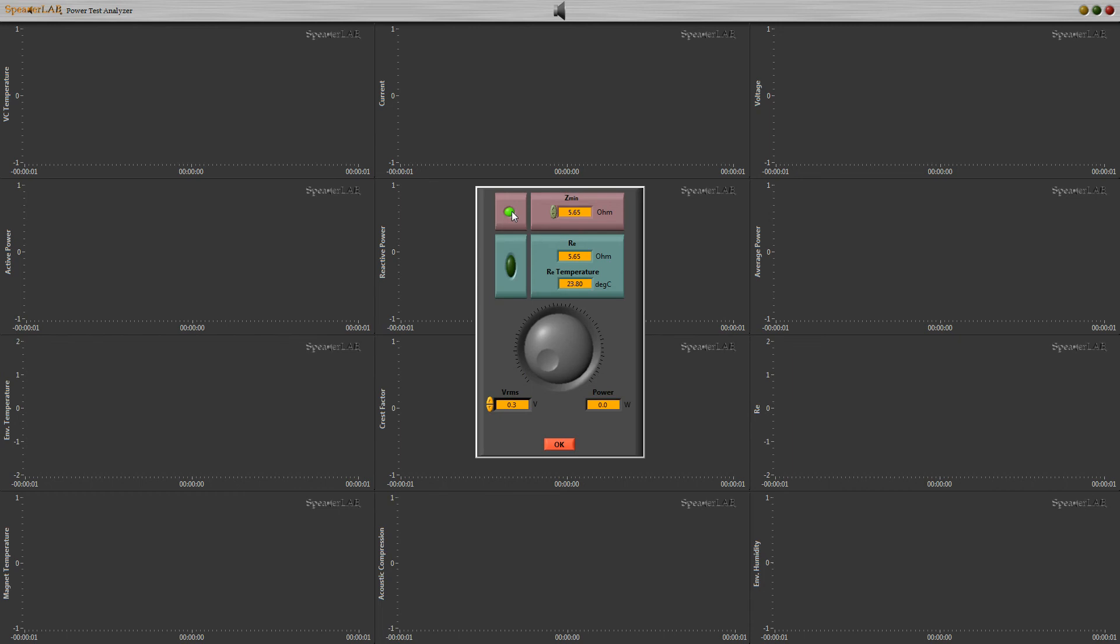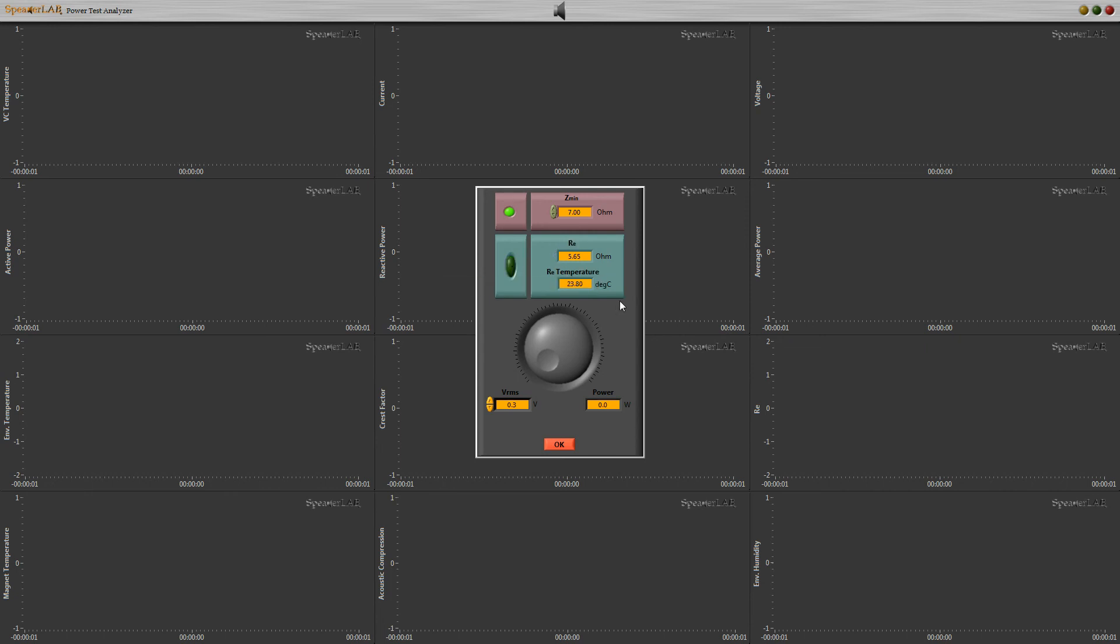In box 6, we can enable minimum impedance control in order to allow average power measurement on minimum impedance. We can also modify and force voice coil resistance and its temperature. This is useful in case the device has different temperature compared to environment. For example, when the loudspeaker is hot from a test previously performed, or is cold because the test chamber has a higher temperature compared to external environment and the loudspeaker was not preconditioned. SpeakerLab advises this condition and suggests forcing manual values. We can use original Re and Re temperature measured with SpeakerLab in another session, or measure these values with other instruments.